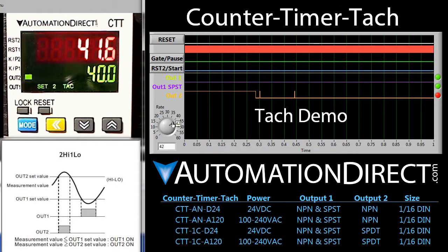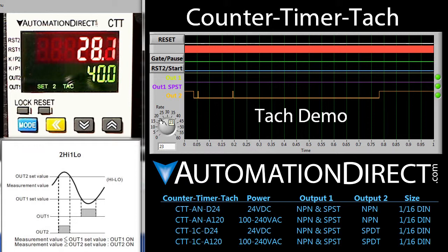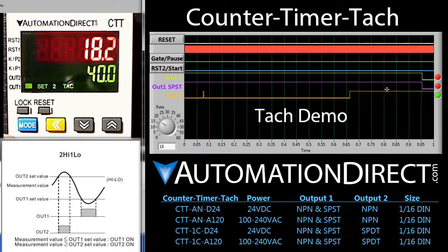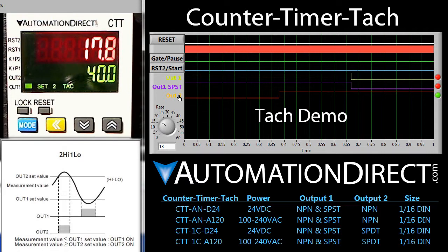If we drop back down it goes inactive – and we go below 20 – and output 1 becomes active. Note that active in this demo is low – that's because these are both NPN outputs – or sinking outputs.